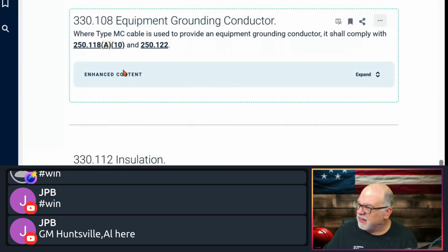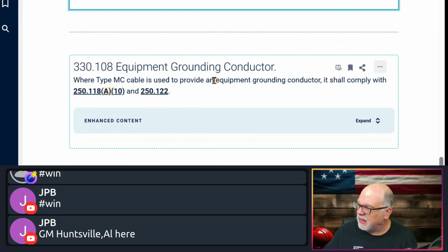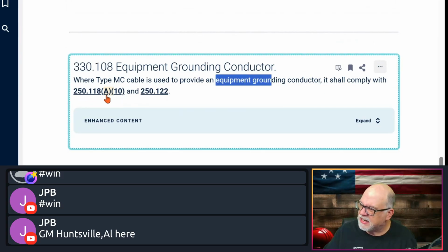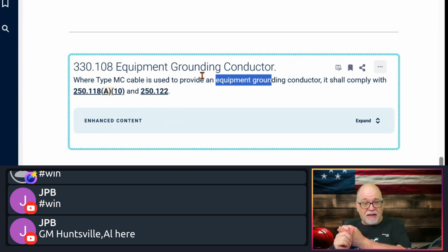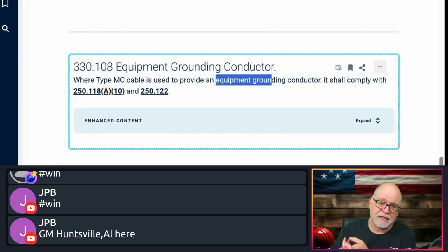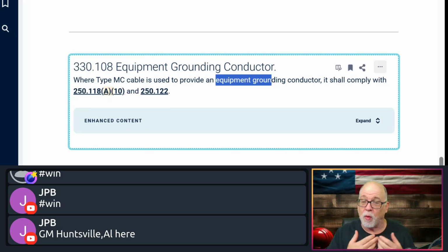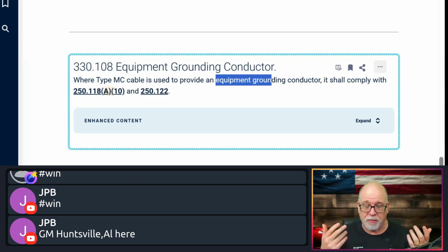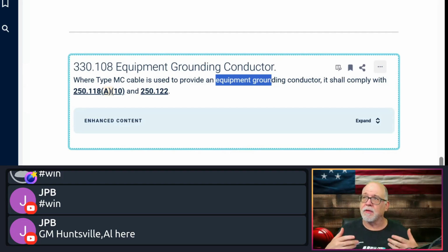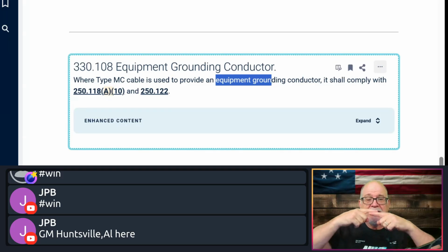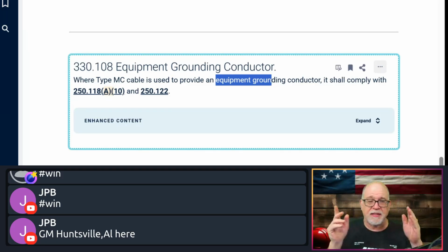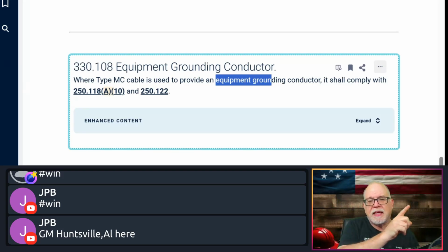Equipment grounding conductor. It says where type MC cable is used to provide an equipment grounding conductor, it shall comply with 250.118(A)(10) and 250.122. Obviously, 250.122 is based on the size of the overcurrent protective device. So that covers the equipment ground that's put inside of the MC cable. All MC cable requires an equipment ground, whether it's the wire type in traditional MC, or you have this new smart ground product, like Southwire has what's called MC AP. Encore Wire and Prysmian have what's called smart ground. That is where you don't have an equipment ground inside of the cable assembly. What you have is an aluminum grounding/bonding conductor that runs outside of the binder, and it makes intimate contact with all the metal convolutions. And when you get to the end, you just snip it off. It doesn't really do any good. All it's doing is making contact with all of the armor.